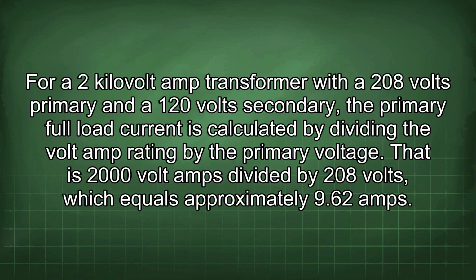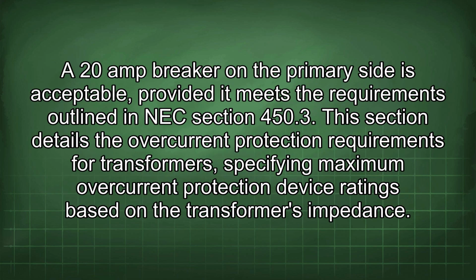For a 2 kVA transformer with a 208 volt primary and a 120 volt secondary, the primary full load current is calculated by dividing the volt amp rating by the primary voltage. That is 2000 volt amps divided by 208 volts, which equals approximately 9.62 amps. A 20 amp breaker on the primary side is acceptable, provided it meets the requirements outlined in NEC section 450.3. This section details the overcurrent protection requirements for transformers, specifying maximum overcurrent protection device ratings based on the transformer's impedance.